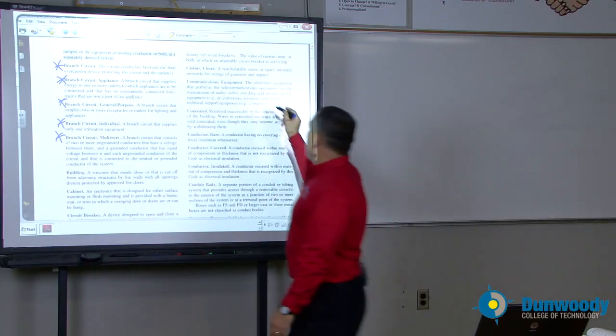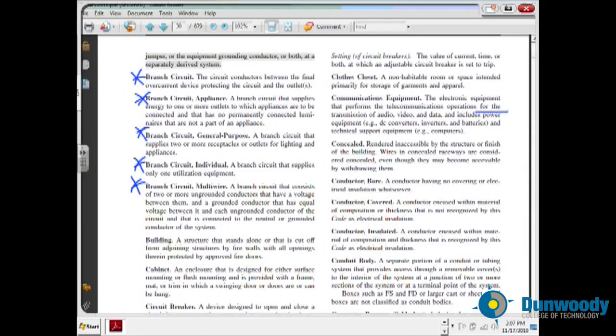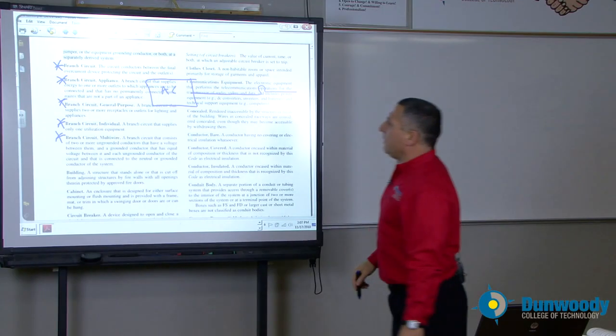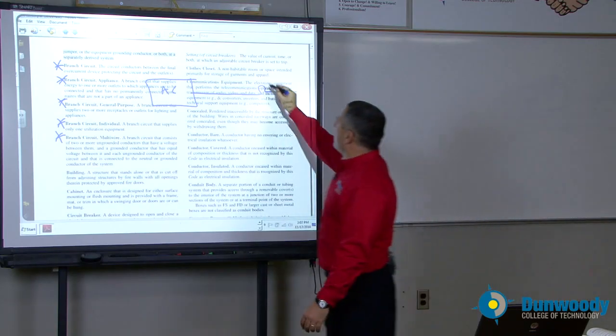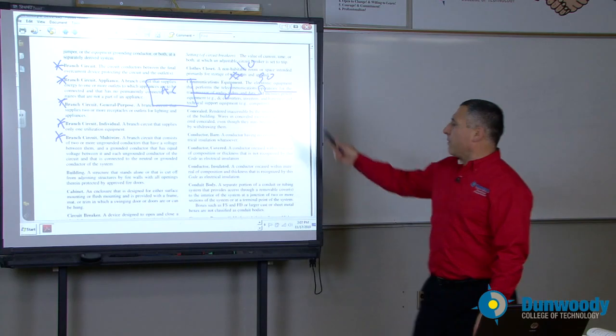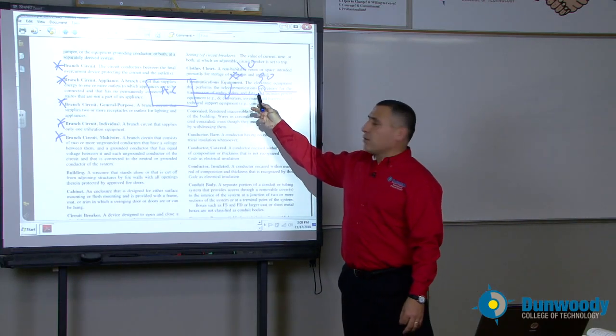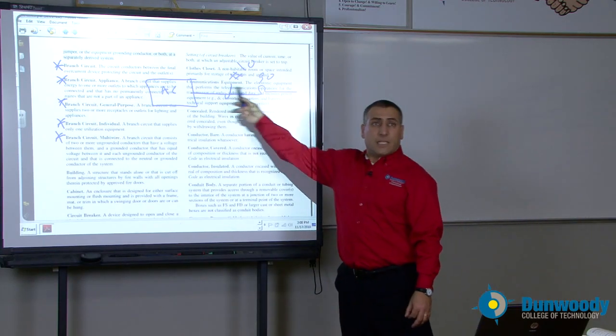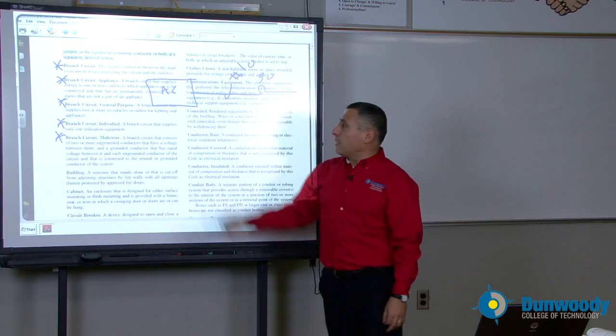Branch circuits: if I have a circuit coming from over here all the way to my nicely laid out AC system, this is a dedicated individual branch circuit. So this was a 30 amp circuit with a number 10 conductor. That's a branch circuit — the conductors between the last overcurrent protection device and the utilization equipment.